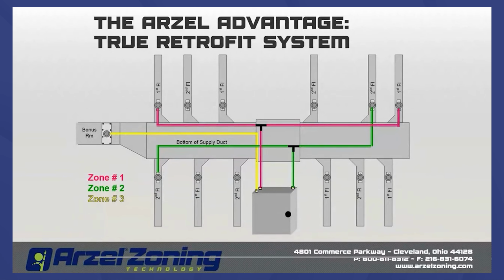The rest of these are all going to be branch style dampers, so the pink tubing and the green tubing. And basically the easiest way is just take your tubing, leave your panel box, go all the way to that last damper in line on that zone. From there, you're going to plug that into your damper, start stapling your tubing and working your way back to the next damper. You're going to cut your tubing, install your T, and just run that right to the damper. And from there, you just work your way back, stapling, cutting the tubing, and adding your T's.